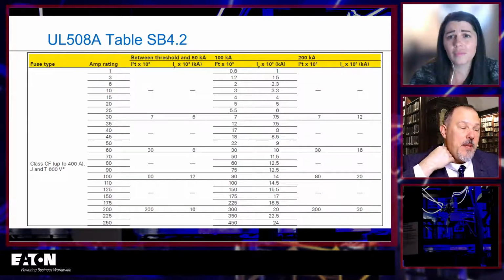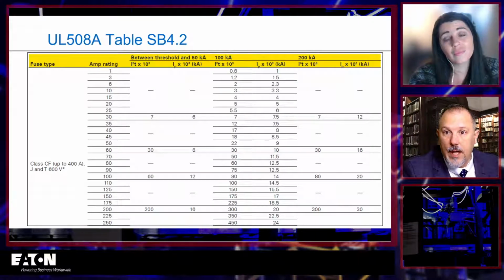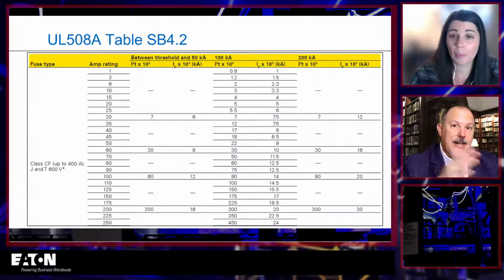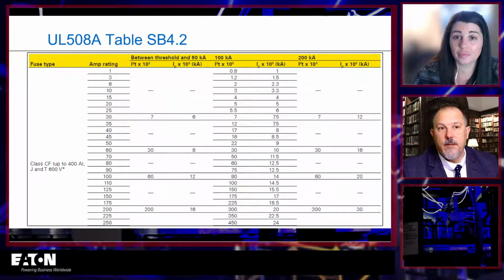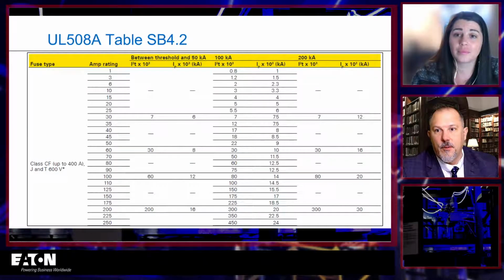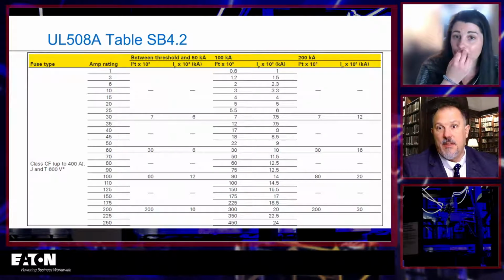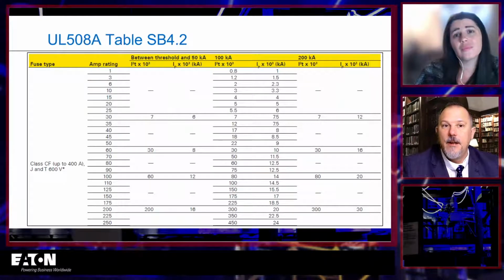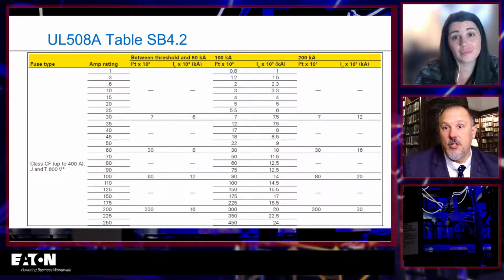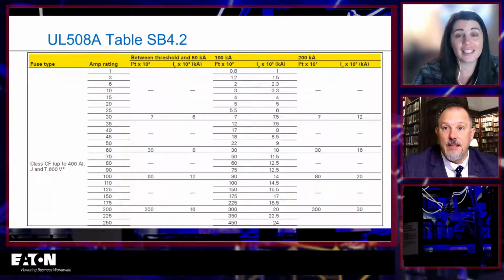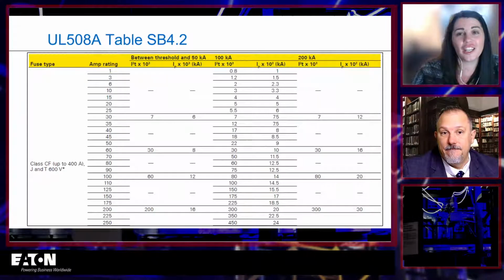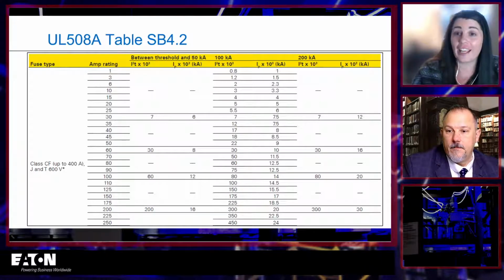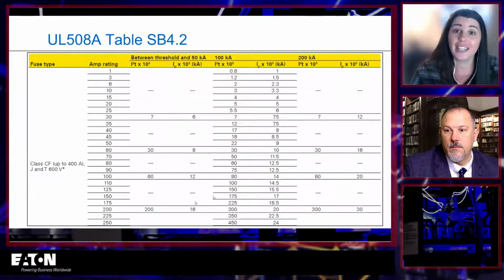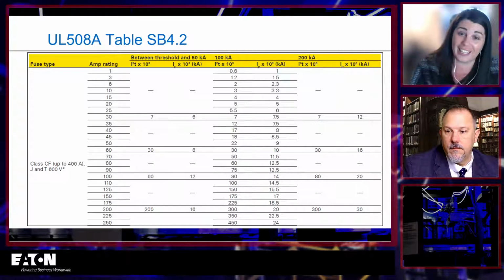And I guess that would be fine if you had things like busway or non-dynamic devices. But if you have circuit breakers or things like that in there, then you really can't use the up, over, and down. You're doing this analysis method basically, and if there's a breaker in there, then that breaker is going to have to be listed with a fuse upstream to say this is what you need. It's just one of those questions where the answer is not a paragraph, right? I can't say yes, I can't say no. The answer is it depends on a lot of things.